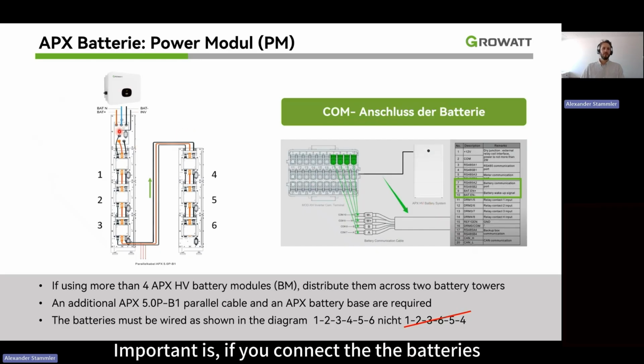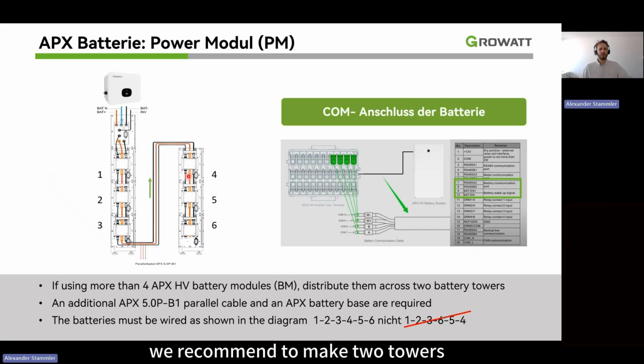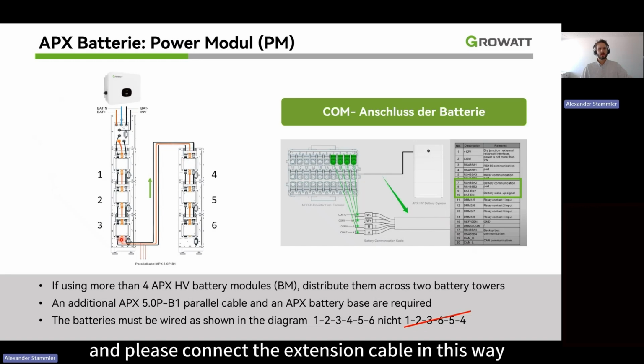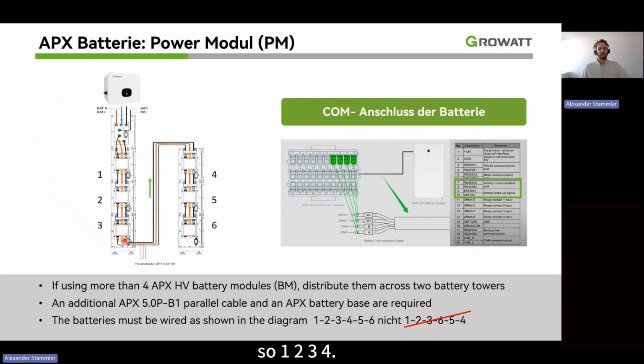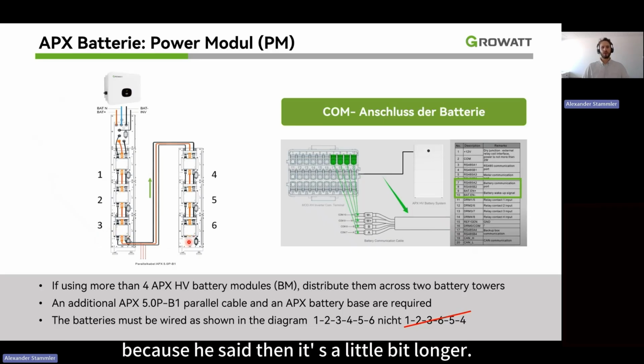Important is, if you connect the batteries and you make two towers, for example, if we have more than 4 battery packs, we recommend to make 2 towers. Then you need this extension cable, and please connect the extension cable in this way. So 1, 2, 3, 4. I had one customer who connected it 3 to 6 because he said then it's a little bit longer. He needed more space, but that doesn't work.